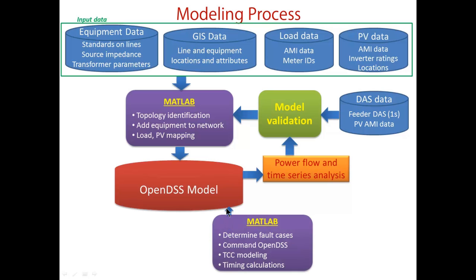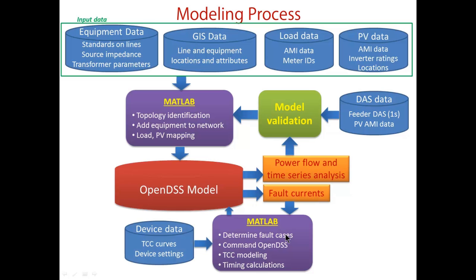We determine all the fault cases that need to be applied through MATLAB, and MATLAB commands the OpenDSS through the COM interface to run each of these fault cases, and from the OpenDSS model, we get the corresponding fault currents, which are input to the MATLAB. MATLAB compares these fault currents with the protection device TCC curves, time current characteristics, and the currently used settings. By comparing these with the measured fault currents for the different fault scenarios, MATLAB can determine whether or not the coordination is maintained or is violated. And the same scripts can also be used to come up with a complete design of the various protection settings for different PV penetration levels.